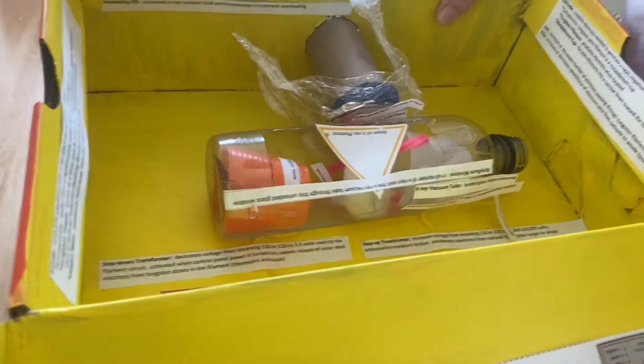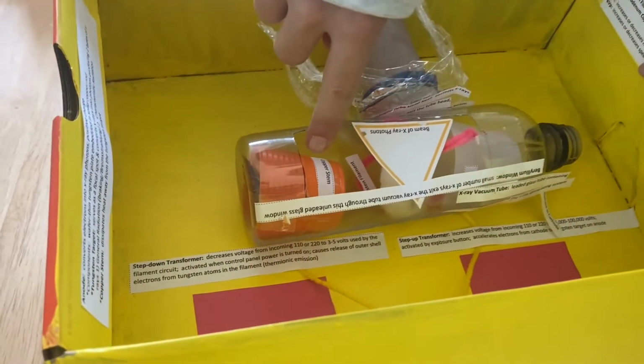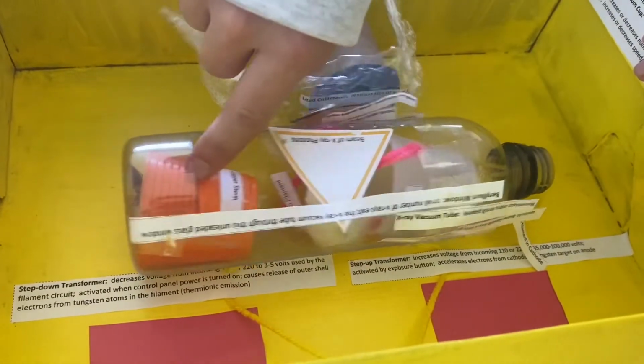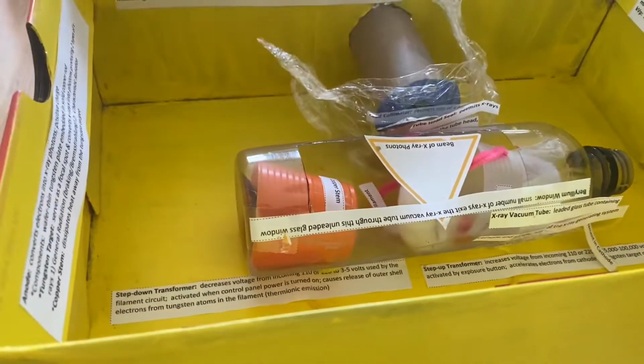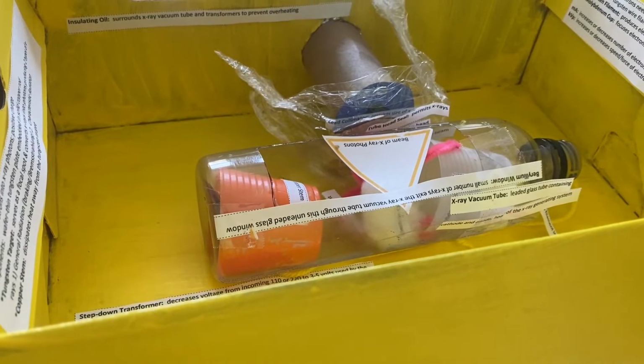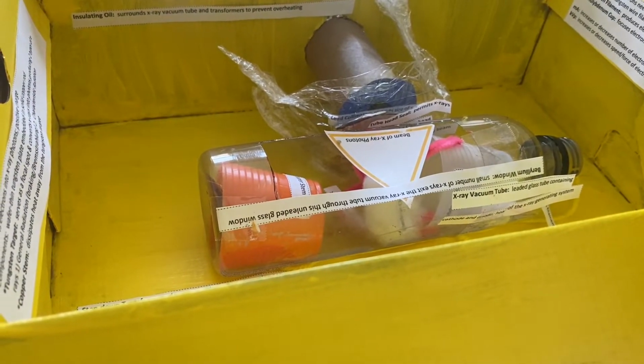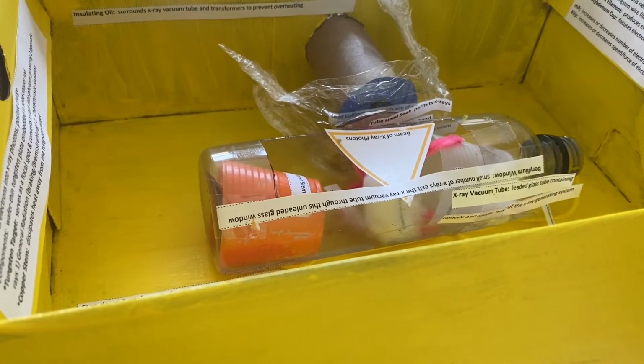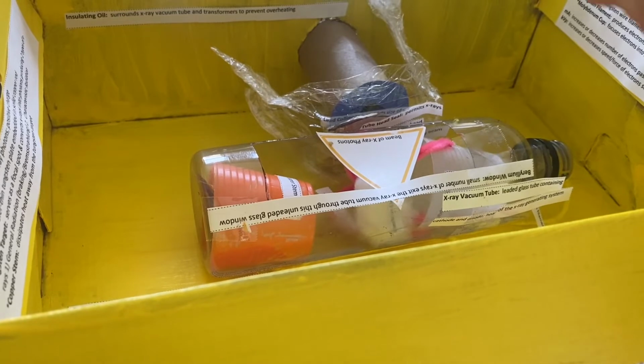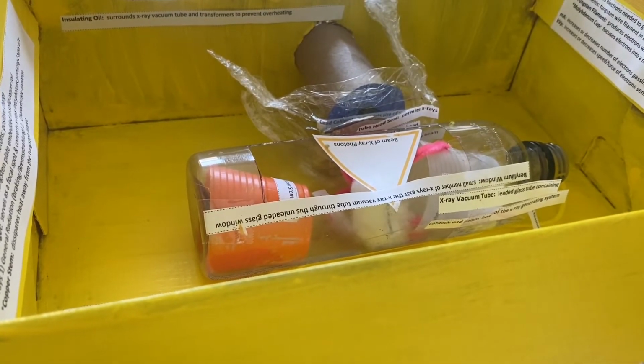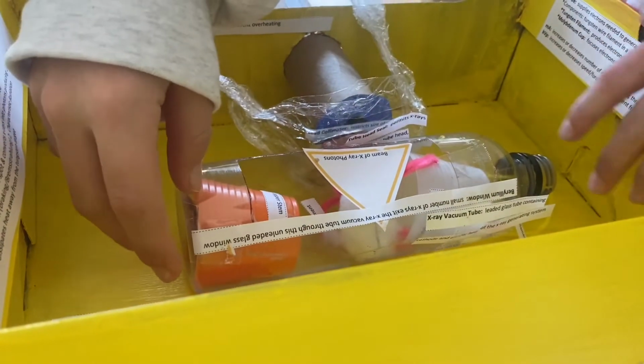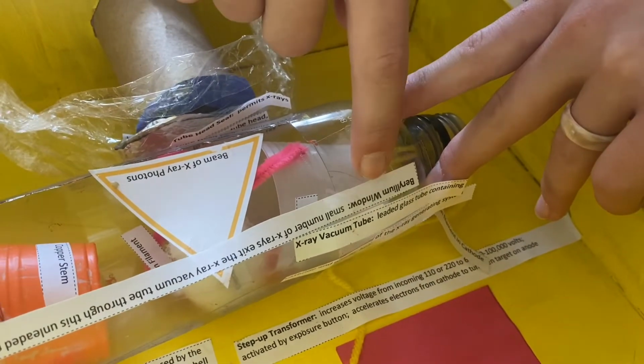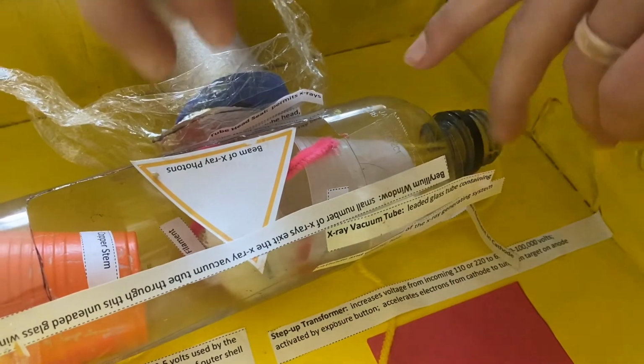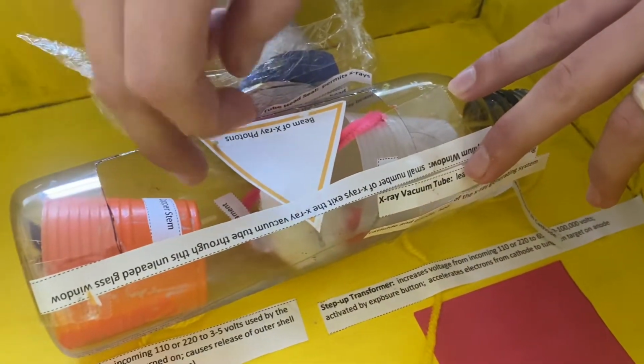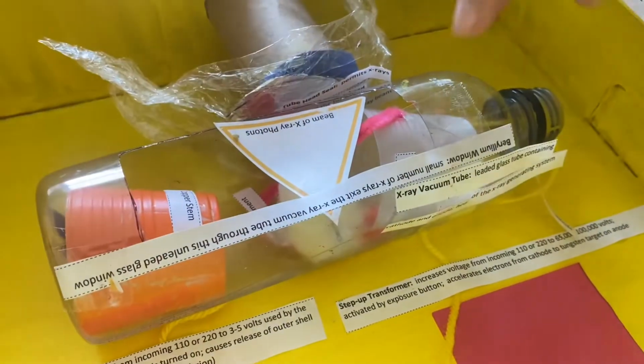Okay, kind of as explained earlier, here is the copper stem, and then the tungsten target is represented by this orange cup. So the tungsten target actually serves as a focal spot, will convert the electrons into X-ray photons, which produces two types of X-rays, the general radiation and the characteristic radiation. The copper stem is what dissipates heat away from the tungsten target. And then if we look right in here, we have the beryllium window, through which a small number of X-rays exit the X-ray vacuum tube. This is an unleaded glass window. So it's unleaded.